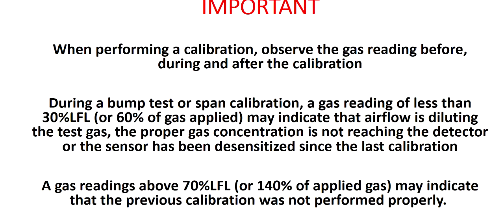It is important that when performing a calibration, you observe the gas reading before, during, and after the calibration. When the gas reading stabilizes, and if it is less than 60% of the test gas concentration being applied, this may indicate that airflow is diluting the test gas, the proper gas concentration calibration is not reaching the detector, or the sensor has been desensitized since the last calibration. A stable gas reading above 140% of the test gas concentration being applied may indicate that the previous calibration was not performed properly.